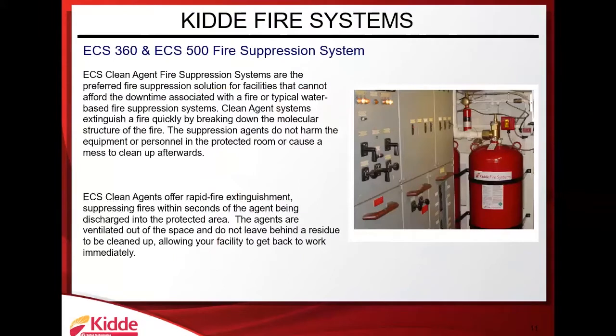This is the first model of fire suppression systems we have: the ECS 360 and the ECS 500. 360 and 500 stand for the pressure at which the agent is stored when filling the cylinder, so 360 psi or 500 psi, which is how the agent is stored in the cylinder.